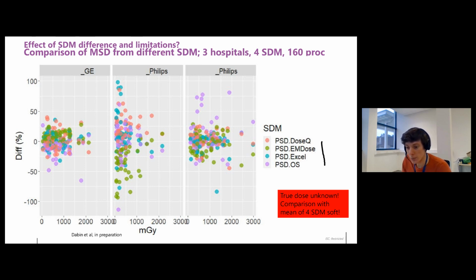And then we plotted the average value of the skin dose calculated for one procedure for 4 different software. And for each software, we plot the difference. So you can see it varies a lot depending on the system and on the software. You can see that for the GE system, the skin dose estimates don't differ too much from the average. So okay, it's within 40%.